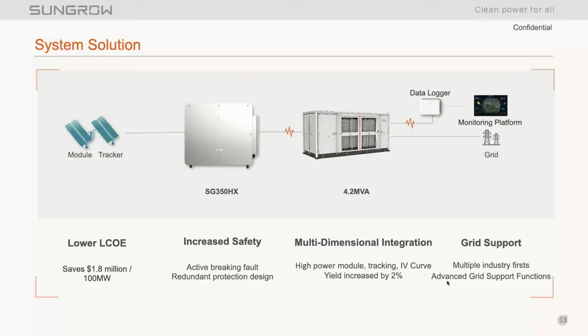The 350, as with the 250, is meant to be installed in a distributed generation format. So the optimized block size that we're looking at for North America is right around 4.2 MVA, somewhere thereabouts. You obviously have room on either end of that point with the 350.